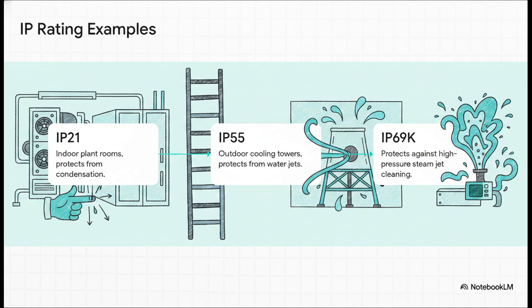Step 1, IP21. This blocks solid objects over 12 millimeters, so fingers, and vertically falling condensation. It's your basic, everyday standard for clean, indoor plant rooms. Step 2 bumps us up to IP55. Now we're blocking limited dust ingress and low-pressure water jets from absolutely any direction. You definitely want this as your baseline for outdoor cooling towers or variable speed drives sitting out in the elements. And then step 3, the absolute extreme, IP69K. This means the enclosure is completely sealed tight against dust and can take a massive beating from intense, high-pressure, high-temperature washdowns.